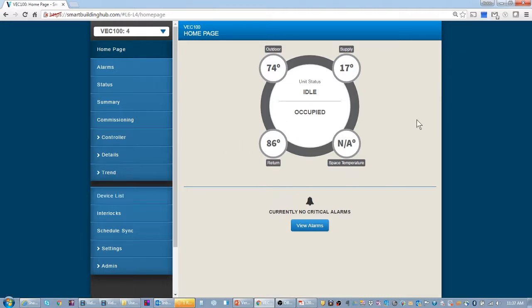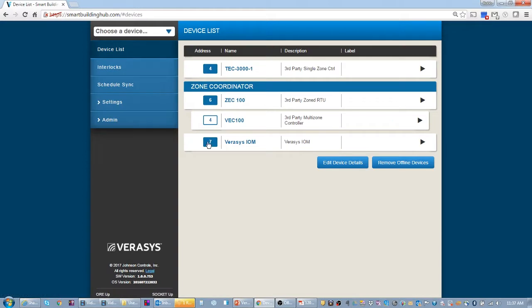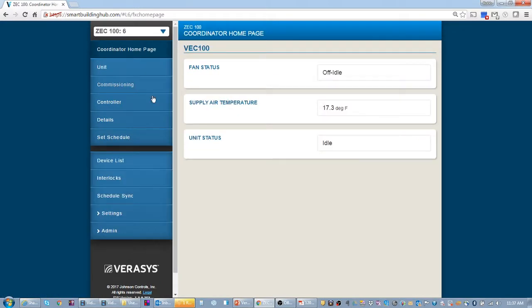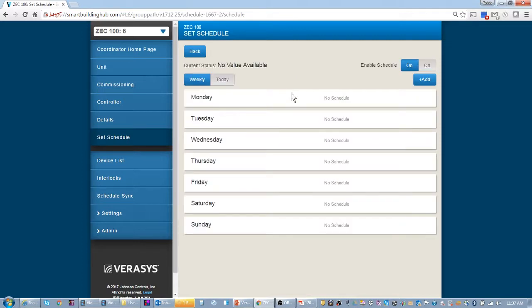The other thing too, we noticed that this rooftop unit controller isn't running right now. So let's get it running. One of the things that I can tell you is going on is because I know that the occupancy schedule hasn't been set. So let's set an occupancy schedule.